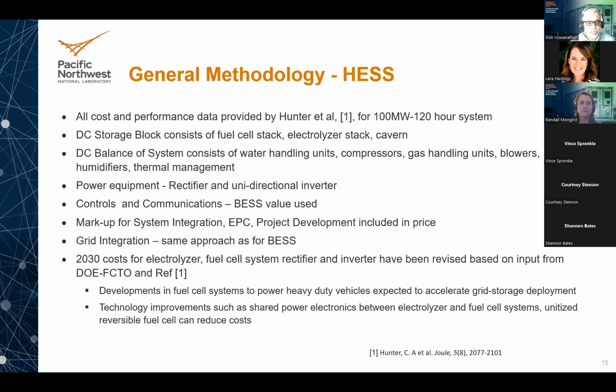For the hydrogen energy storage system, most input came from NREL or the Fuel Cell Technology Office, with cost data taken from reference 1. The DC storage block consists of the fuel cell stack, electrolyzer stack, and the cavern to store hydrogen. The DC balance of system includes water handling units, compressors, gas handling units, blowers, humidifiers, and thermal management. Power equipment here is a rectifier for charging and a unidirectional inverter for discharge.